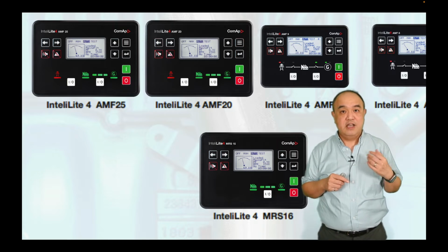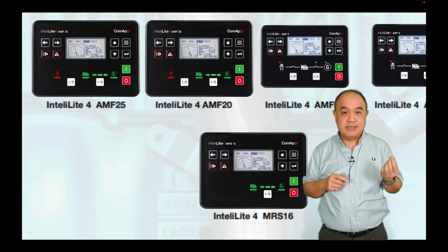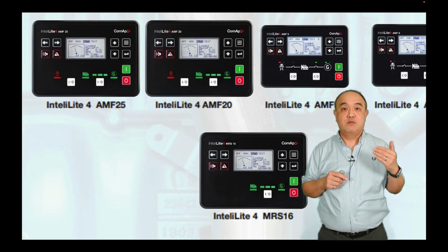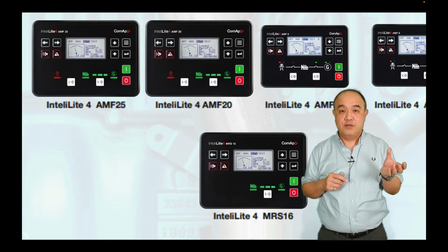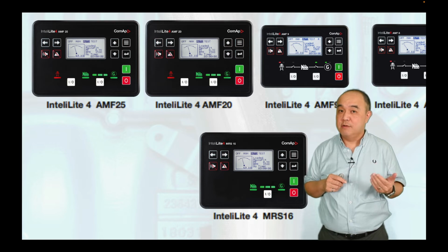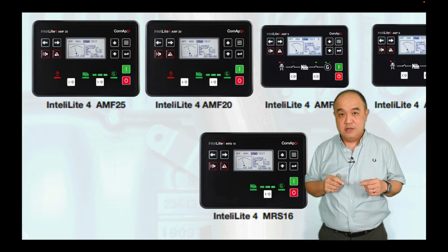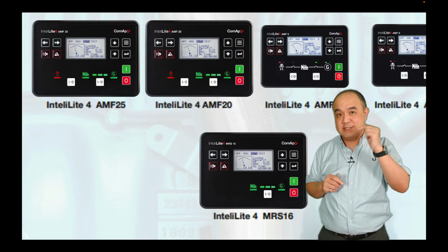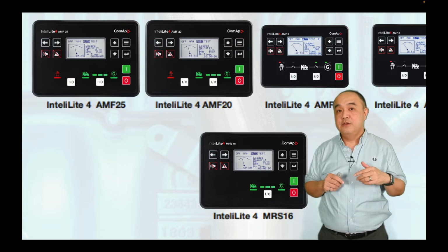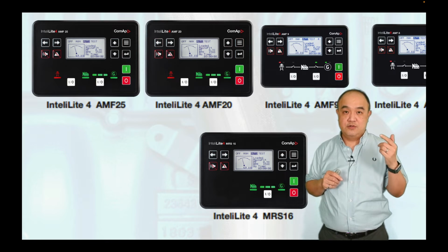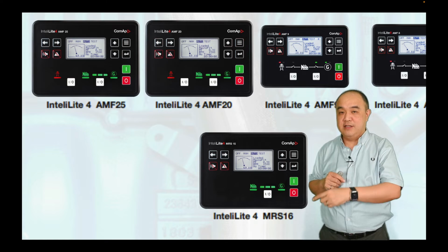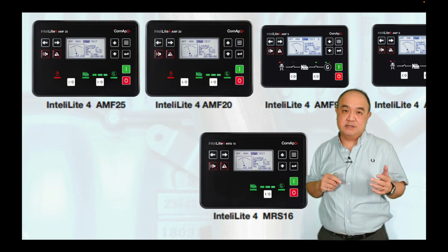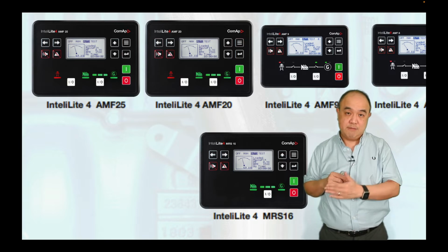What is MRS? AMF is automatic mains failure, which means the AMF controllers detect the mains voltage, and when there's a mains voltage fault, they switch on the genset automatically, switch over your ATS, and do a fully automated system like that. The MR system is what we call manual remote start. So you can press the button to manual start, of course, but you can also use remote start signals to start your genset. Now, you can program the AMF controllers to use as an MRS, but you can't go the other way around. You can't take an MRS controller and make it AMF because it doesn't measure mains voltage at all for the MR series.